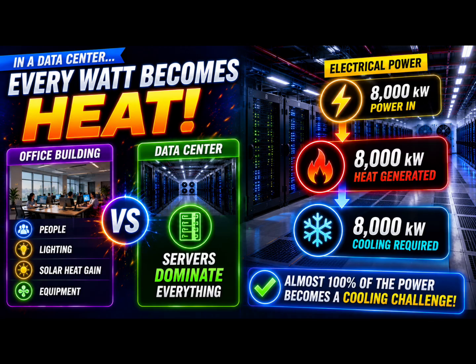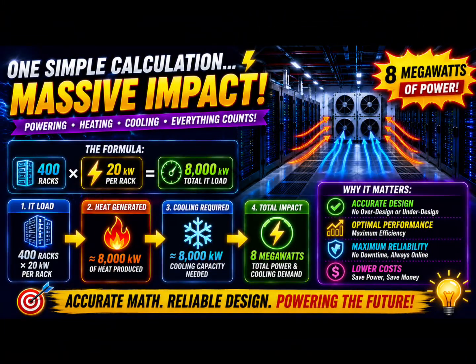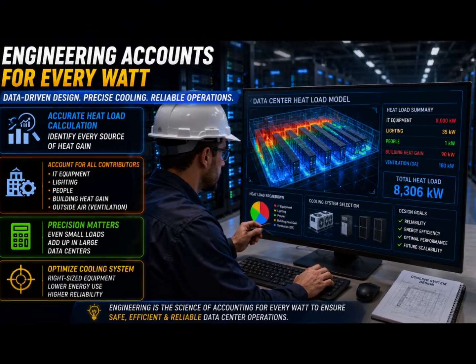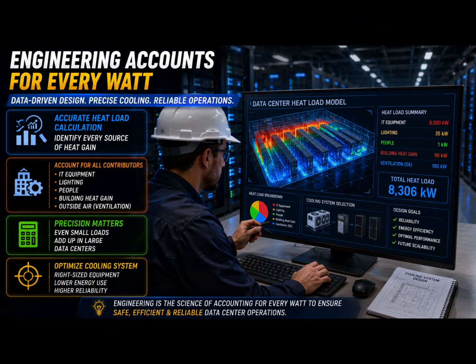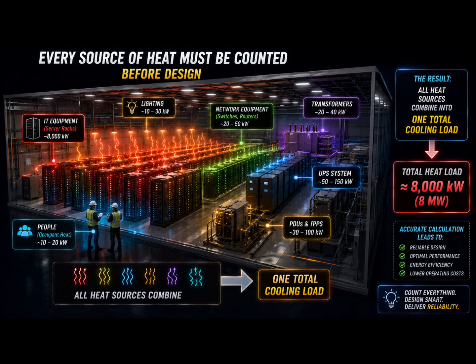Almost every watt consumed by the equipment is eventually released as heat, which means our 8 megawatt electrical load very quickly becomes an 8 megawatt cooling problem. But engineering never stops at the largest number. Professional designers know that ignoring the smaller heat sources can lead to inaccurate equipment selection, reduced efficiency, and unnecessary operating costs. So before we size a single cooling unit, we must account for every source of heat entering the room.